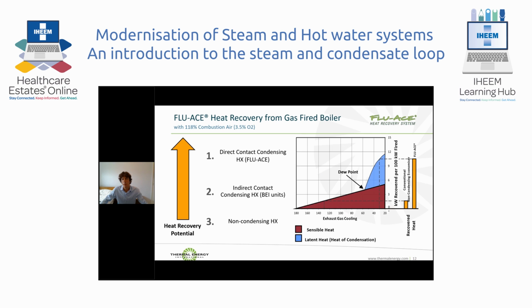We can see the same graph here again. The red area represents the sensible energy, the temperature reduction of the exhaust, and the blue area is the condensing energy, where we get the latent energy released as we condense the water vapor into water. This scale on the right-hand side is kilowatts recovered per 100 kilowatts fired. Essentially, it's a percentage. Typical non-condensing economizers can achieve 2 to 3%, reducing the exhaust gases to a maximum of about 120 degrees C.